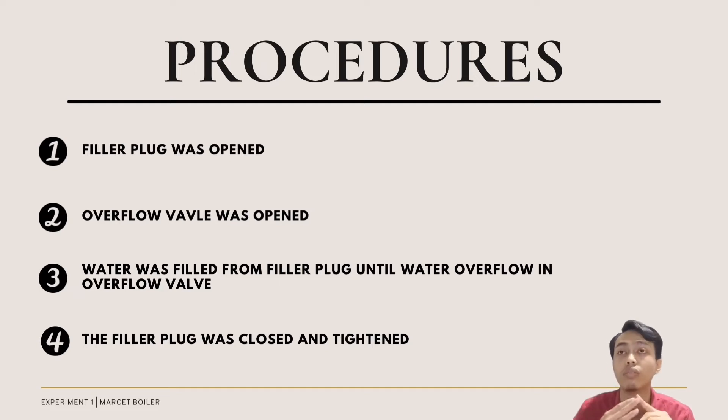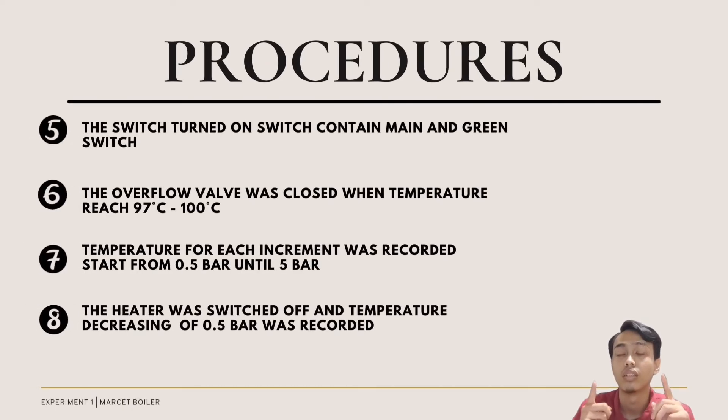Switch on the switch in the control panel which contains the main and green switch. Once the temperature reaches the range 97 to 100 degrees Celsius, close the overflow valve. Then each increment of temperature will need to be recorded starting from 0.5 bar until 5 bar. The last step is when the pressure comes to 5 bar, switch off the heater. And record every temperature decrease at 0.5 bar intervals. All data will be recorded in Table 1 below.